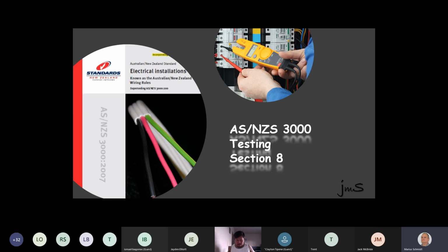Now you all want to be electricians. Some of you guys got a lot of experience. Some of you got about 3 to 3.5 years experience. Those that come from overseas, the test instruments you use overseas are the same test instruments we use in New Zealand. Now please, do not say megger. If I say to you a complex test instrument, it means it's a big box where you put everything in and you select the scale: ohms, impedance, RCD, fault loop. You know with me? But it's important to select the right scale.